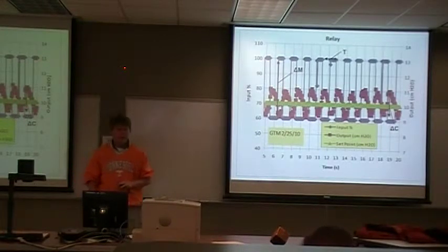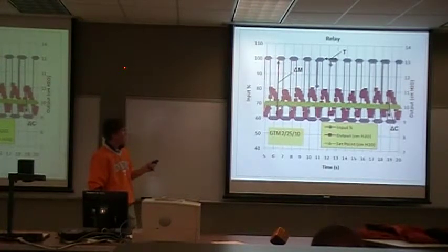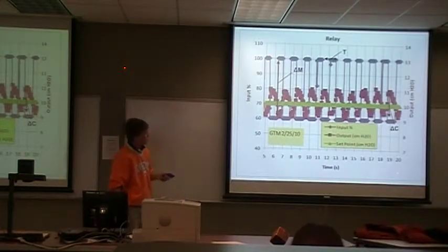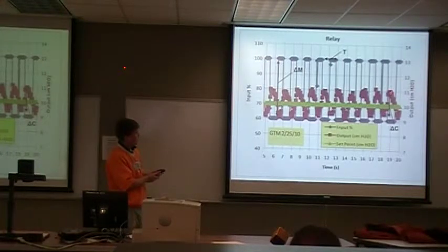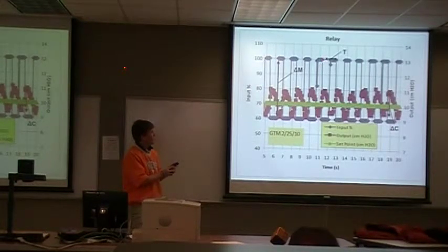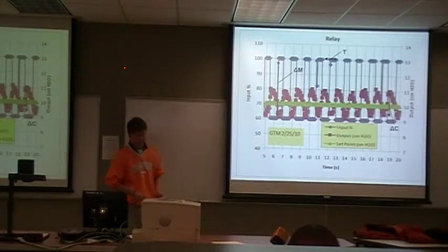There are three main parameters we needed from the relay response. That is delta M, which is the difference between the two input values we put in; delta C, which is the difference between the highest-valued output versus the lowest-valued output; and the period, which spans from the point where the input value changes back to that same point in the cycle.